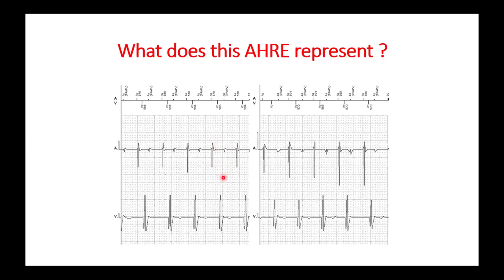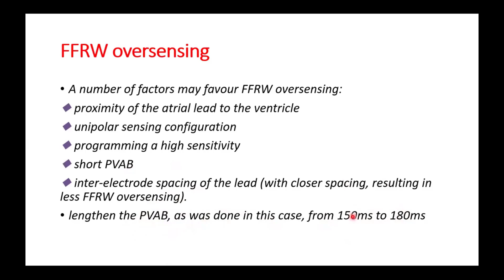Here are the factors which favor R wave oversensing: unipolar lead programming, placing the atrial lead in close proximity to the ventricle during implantation, making the atrial lead very sensitive by programming high sensitivity, and programming a very short post-ventricular atrial blanking. So the key to overcome this is to prolong the post-ventricular atrial blanking, usually programmed from 150 milliseconds to 180 milliseconds.